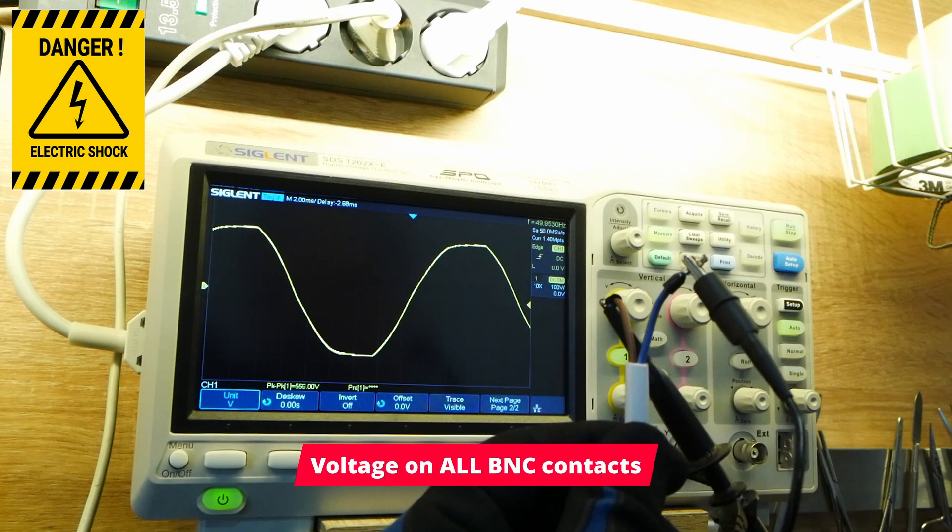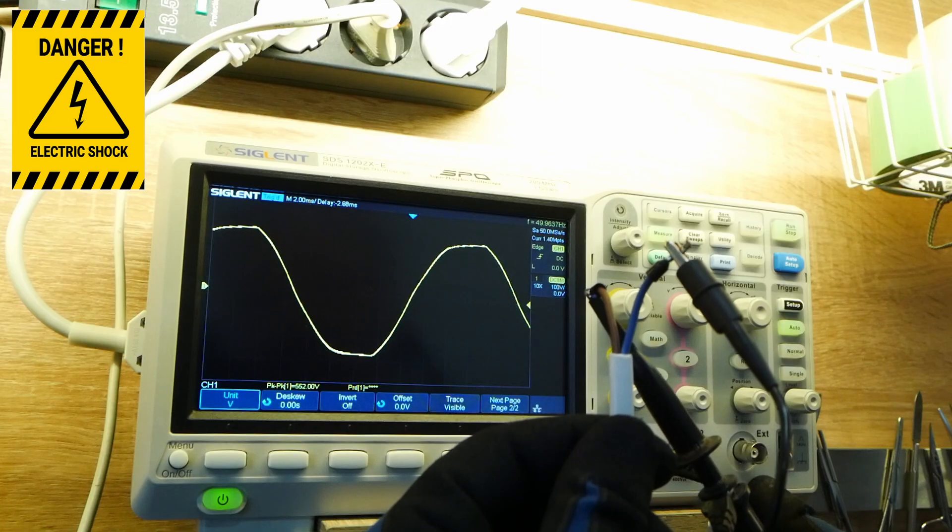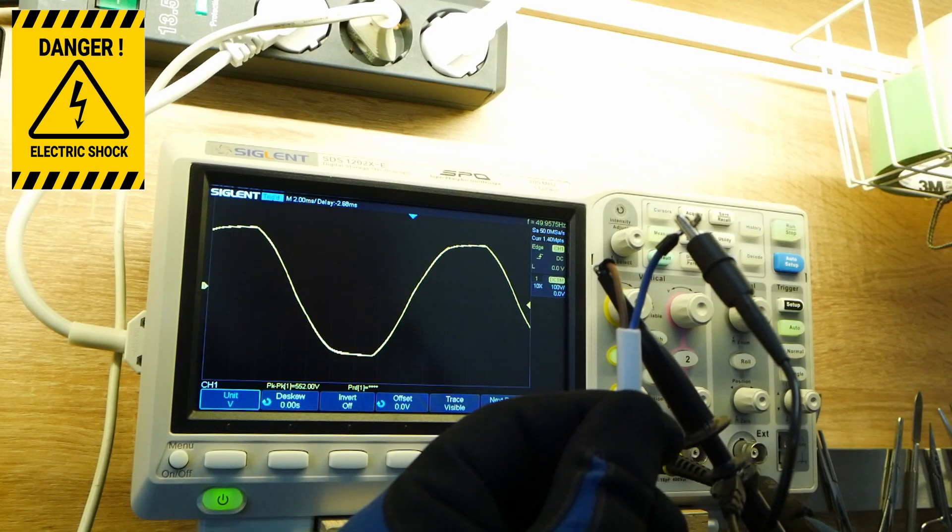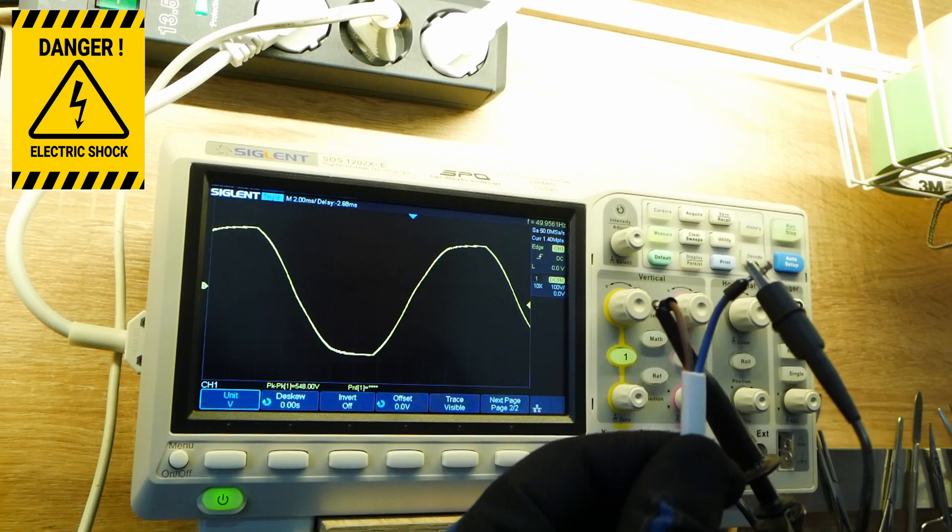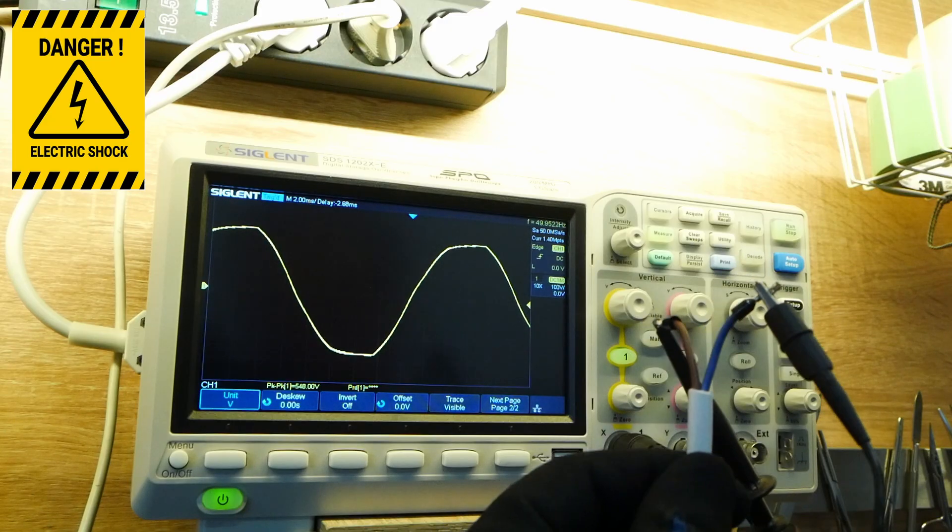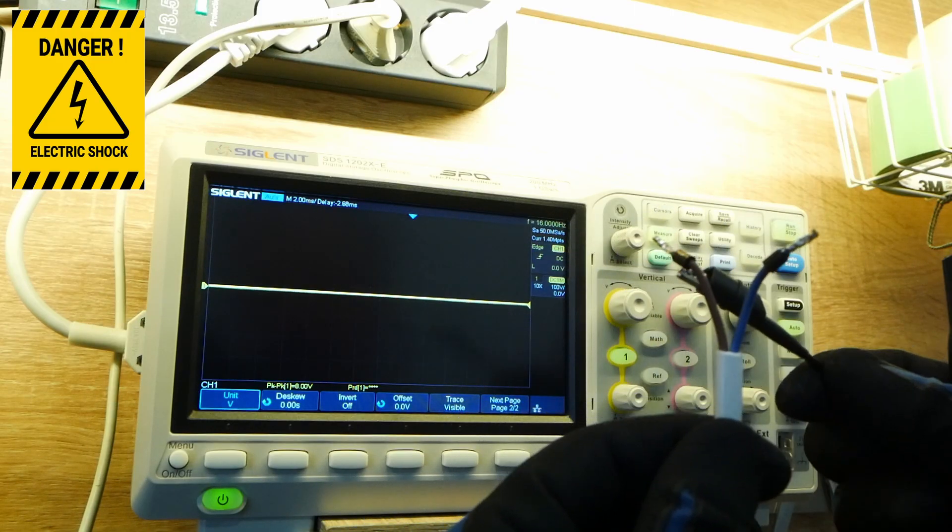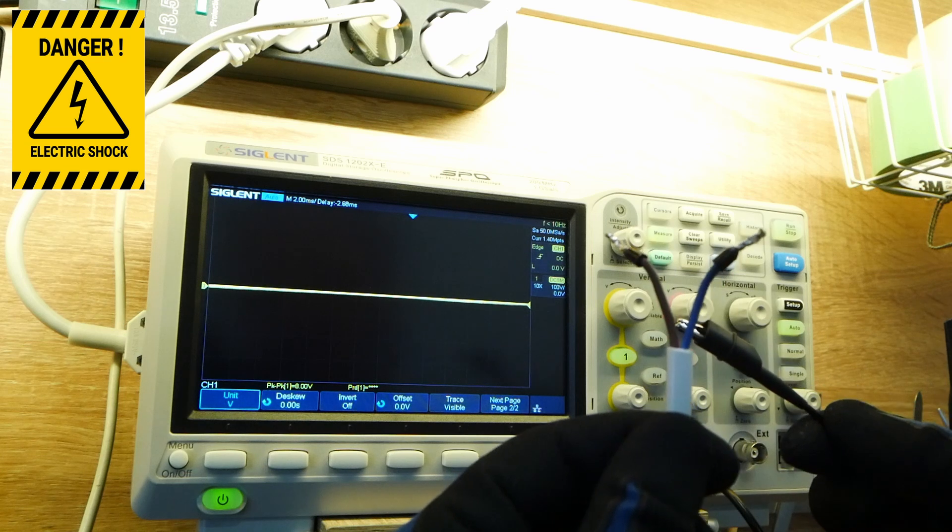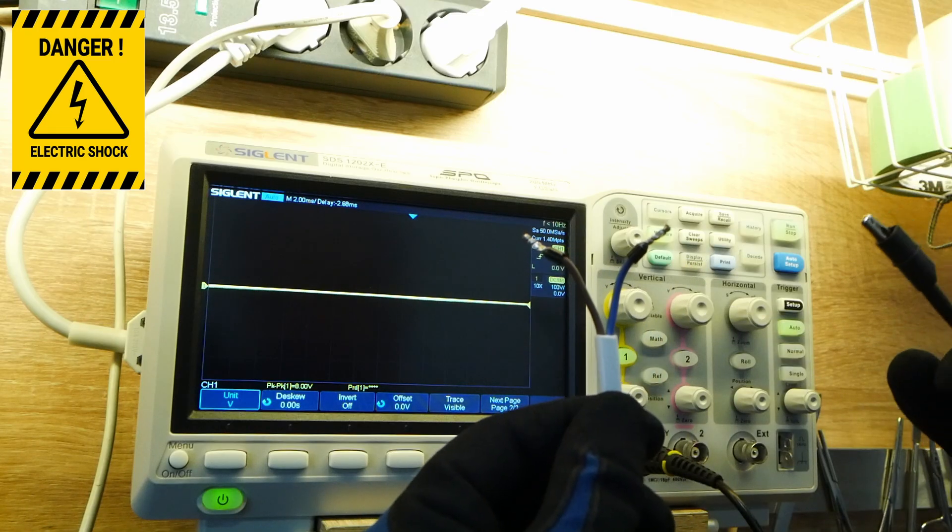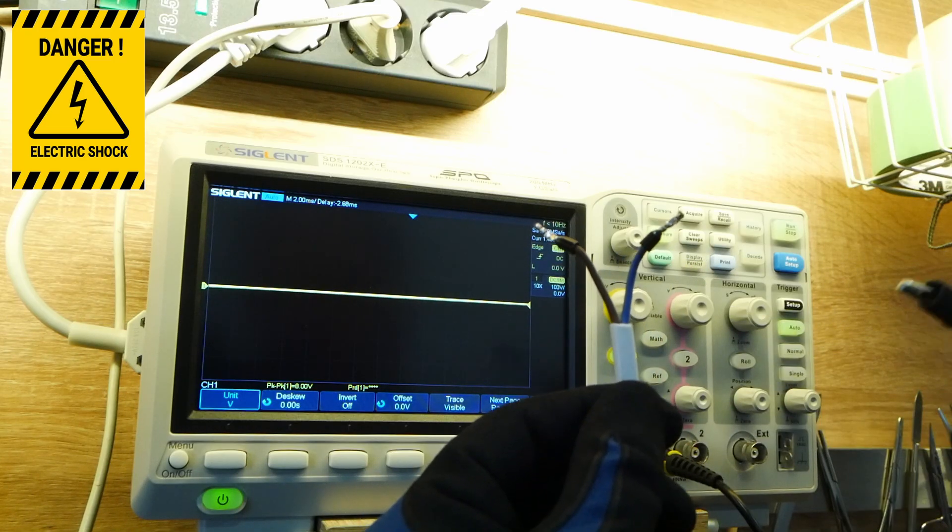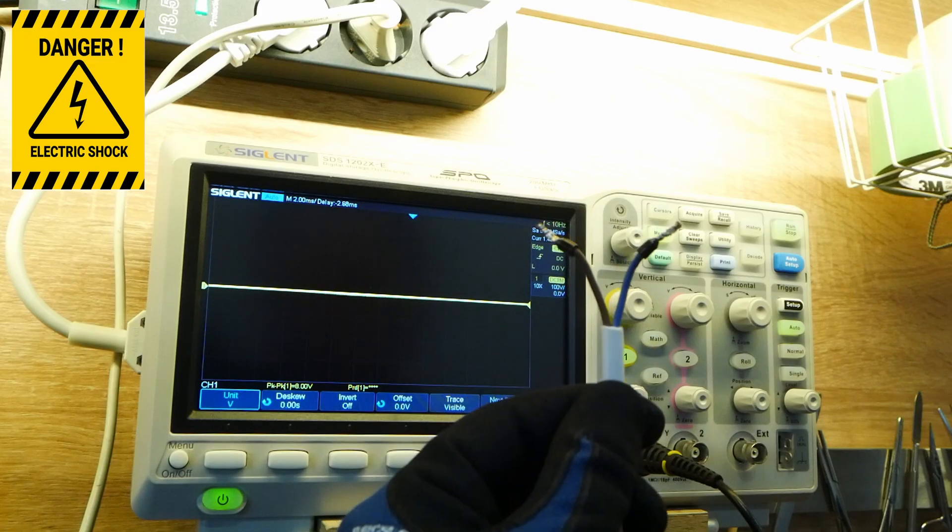Yes, just know that right now we have live on these contacts. And what else? Well, most critical thing is do not connect your crocodile on the live wire—you will create a short path. Pretty much that's it. Check the wire before you connect your crocodile. Then, only then, you can connect it, because if I connected the crocodile wire to the live wire right now, I would create a short.